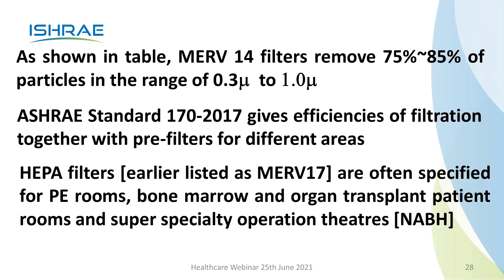We'll come to that. HEPA filters, the HEPA filter efficiencies are based on MPPS. MPPS stands for most penetrating particle size. For this particle size, the filter exhibits its lowest filtration efficiency. That means when we say 99.99% at 0.3 micron, for particles which are a little smaller than that and bigger than that, the efficiency is in fact a little bit higher than that 99.99. Get this particular thing in your mind.